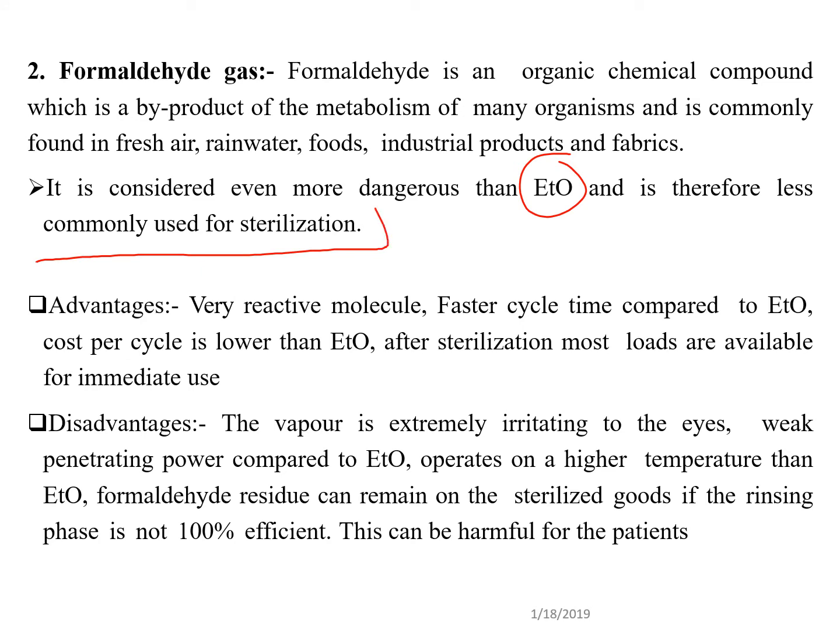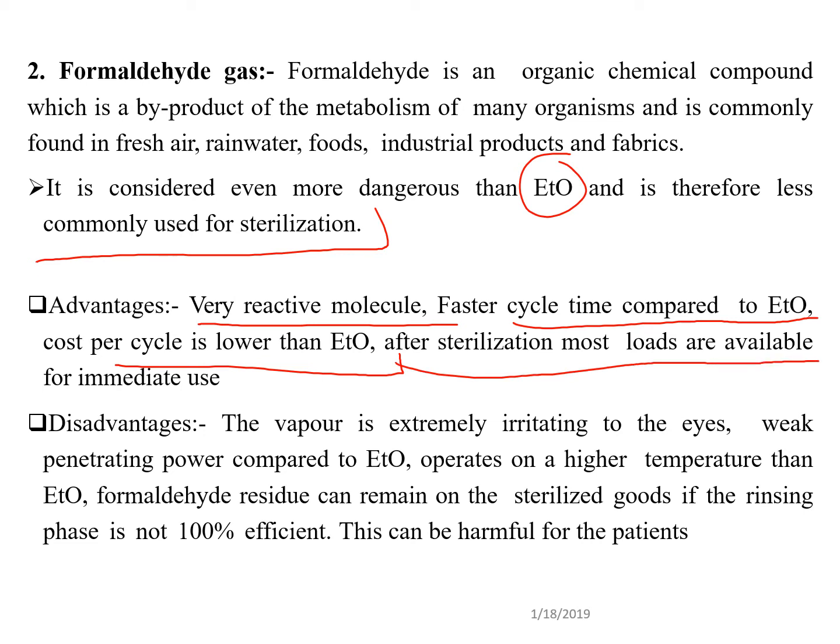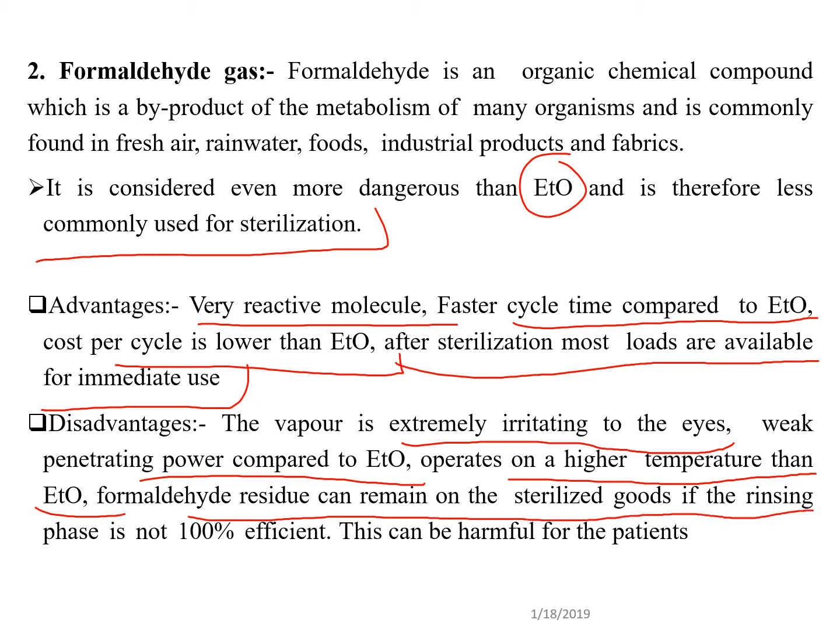The advantage is that it is a very reactive molecule with a faster cycle time compared to ETO. Cost per cycle is also lower than ETO. After sterilization, most loads are available for immediate use. But the disadvantages are that the vapors of this gas are very irritating to the eyes, it has weak penetration power compared to ETO, and it operates at a higher temperature than ETO. Formaldehyde residues can remain on the sterilized goods even if the rinsing phase is not 100% efficient, and this can be harmful for the operators, patients, or whatever workers are working in the laboratory.